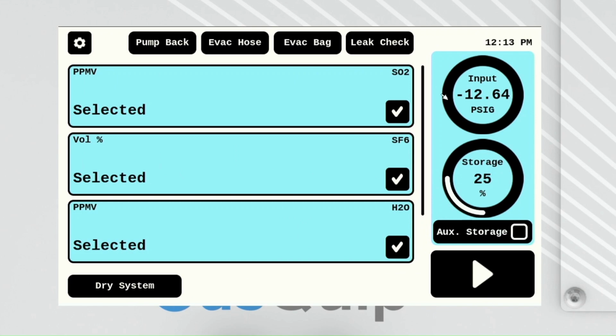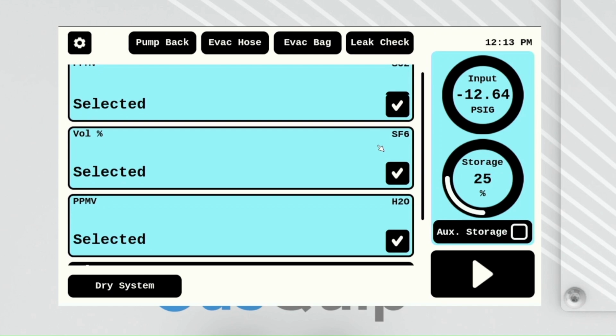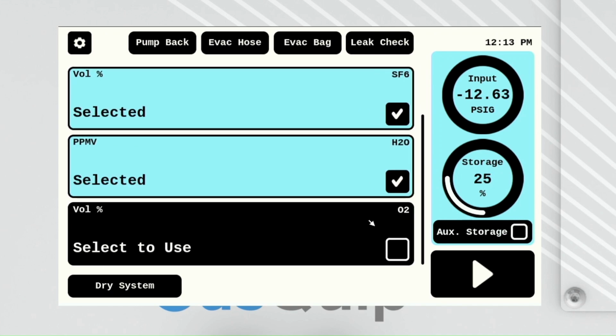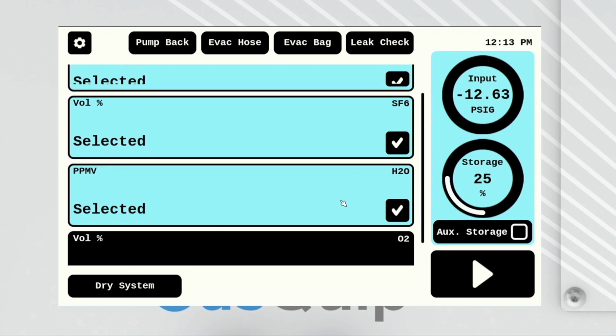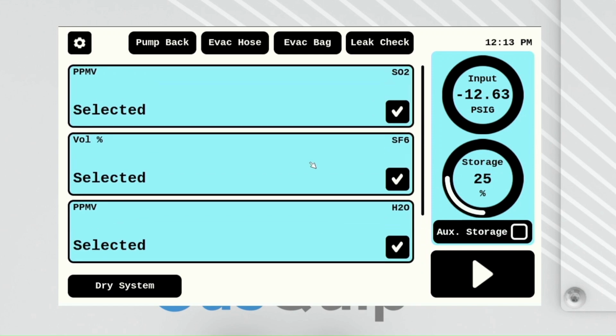Now we can see that our input pressure is negative 12.64 PSIG, so we have a good vacuum on our hose. Seems like it's holding, and we can run a test. Our storage amount here, we've already run one test this week, so our storage is at 25%. That's plenty of storage left over to continue to run more tests. Depending on what we actually want to test for, we can check and uncheck those sensors to be used during the test. I'll leave O2 deselected right now so we can just run a standard 3-parameter test on this gas bottle.